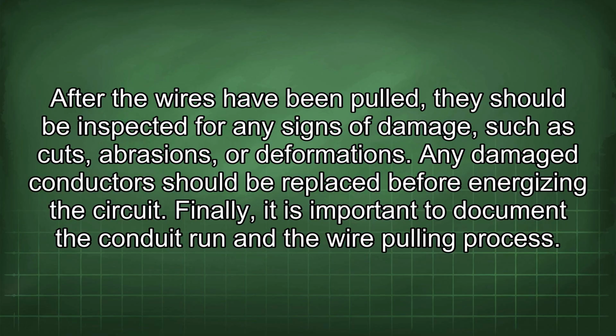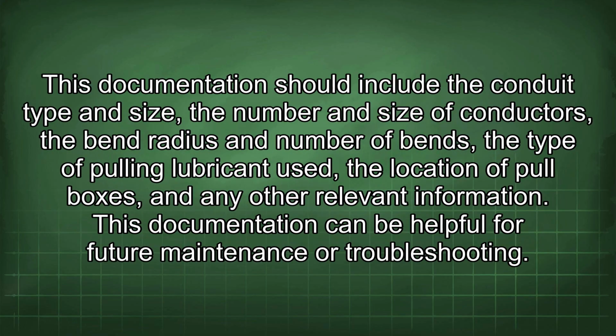Finally, it is important to document the conduit run and the wire pulling process. This documentation should include the conduit type and size, the number and size of conductors, the bend radius and number of bends, the type of pulling lubricant used, the location of pull boxes, and any other relevant information. This documentation can be helpful for future maintenance or troubleshooting.